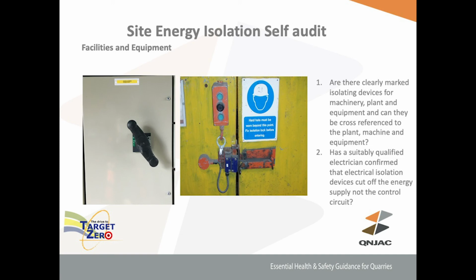As you can see from that photograph next to the isolator, this was actually a good idea which turned out to be possibly not a good idea. You can see the multi-hasp underneath that control box. Originally the site decided that if anybody went inside that machine - you can see the two blue blocks, which are a safety control system called a coded magnet system - to prevent somebody shutting the door and pressing the reset button behind them, they placed a multi-hasp on the door lock and put their padlocks on it, which was actually a very good idea. But what ended up happening was that people were using that multi-hasp and their locks for isolation, so clearly that safety device is not an isolation device.